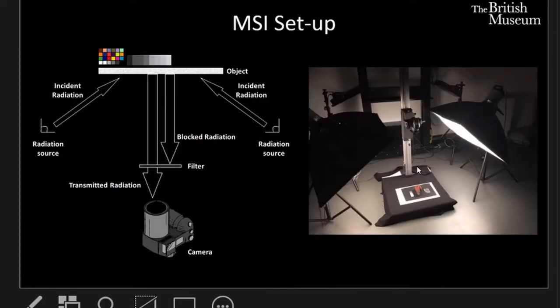In a typical setup for multi-spectral imaging, the incoming radiation — typically light in the UV, the visible or the infrared ranges — interacts with the object. In each case these incoming wavelengths can be absorbed, reflected, and/or absorbed and re-emitted as luminescence. This outgoing radiation is captured by a modified camera where the sensor detects wavelength ranges from the UV all the way into the near infrared, and we select the part of that outgoing radiation we're interested in by placing different filters in front of the camera lens.